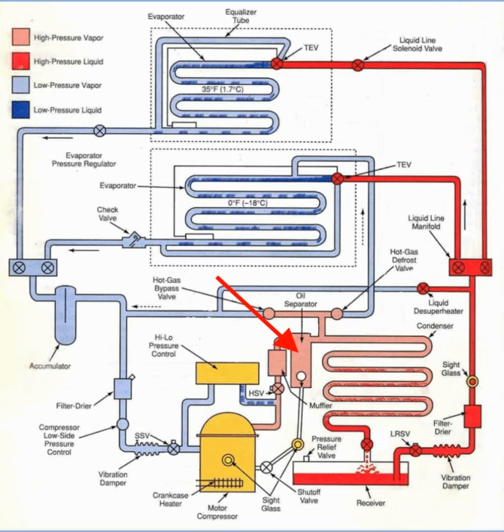In both types, a high oil level opens a float valve, returning the high-pressure oil to the low-pressure side of the compressor through an oil return line.